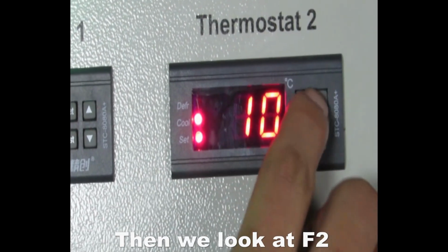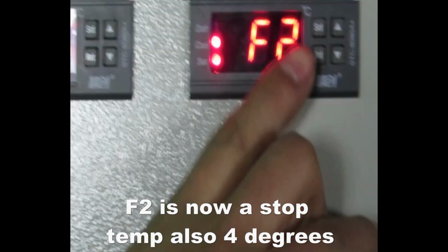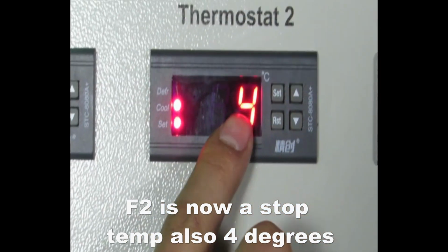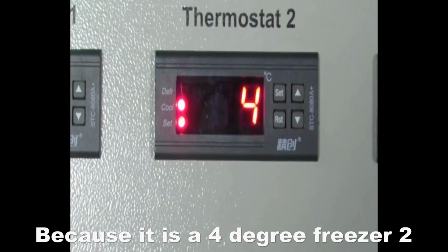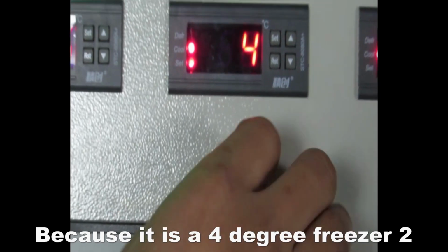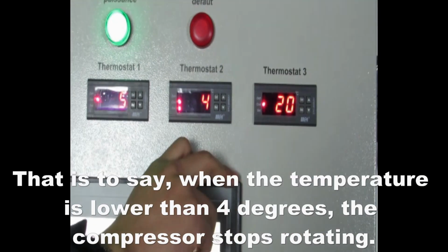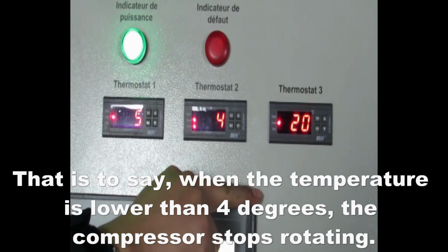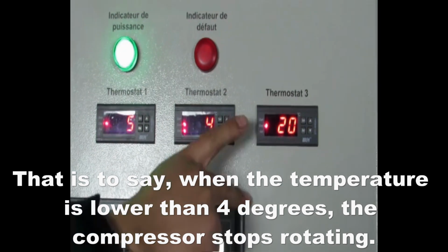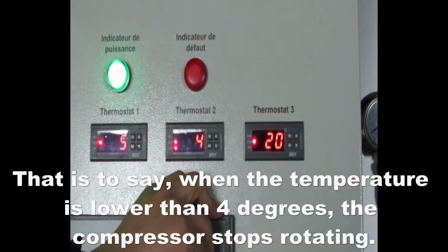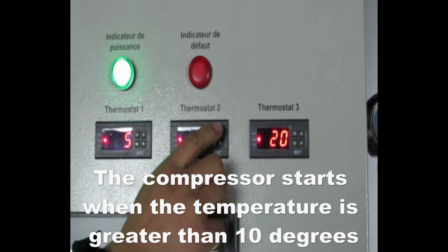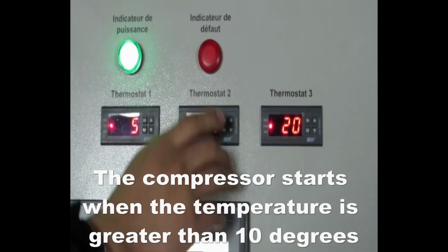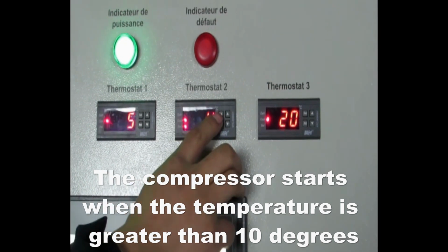Then we look at F2. F2 is the stop temperature, 4 degrees, because it is a 4 degree refrigerator. That is to say, when the temperature is lower than 4 degrees, the compressor stops rotating. The compressor starts when the temperature is greater than 10 degrees.